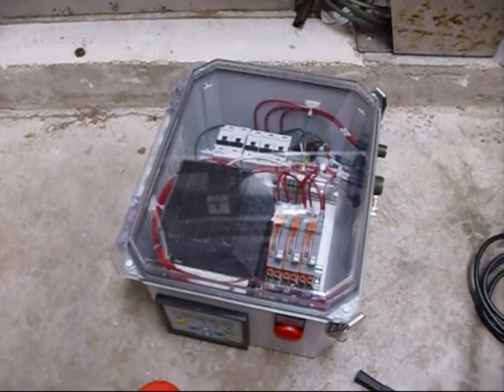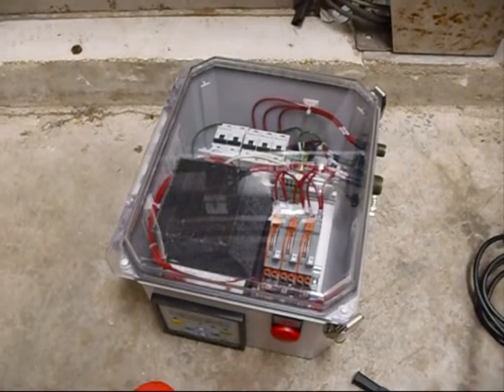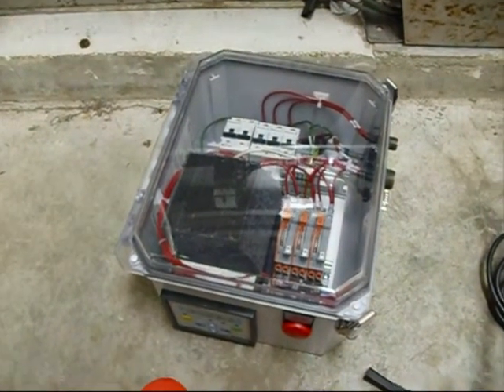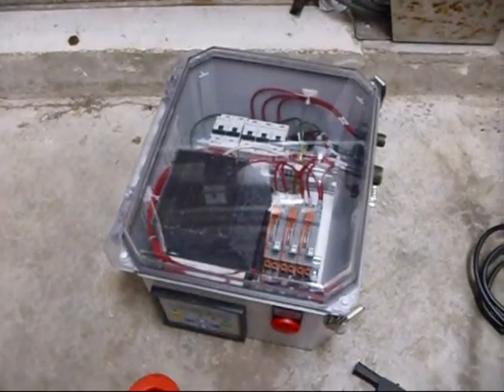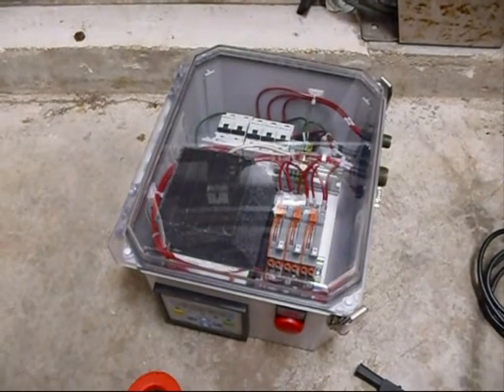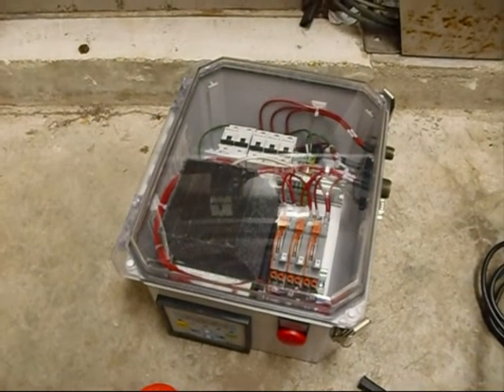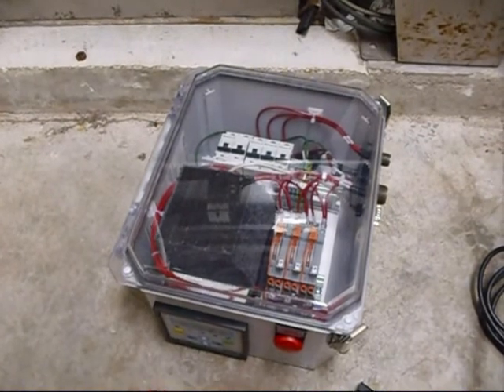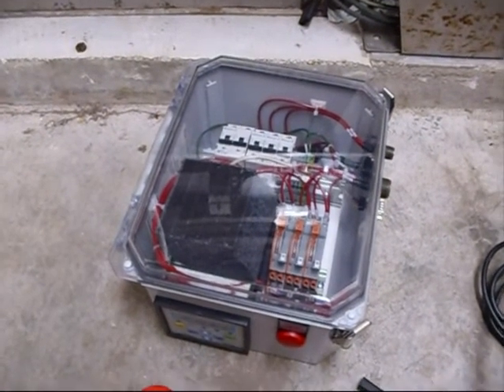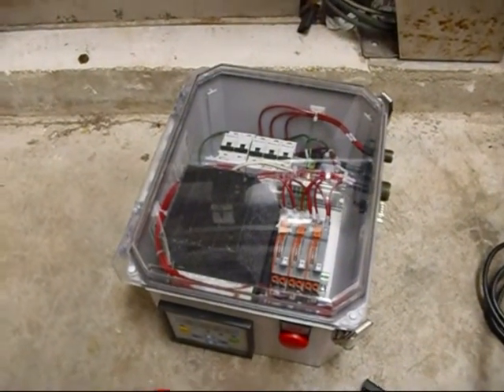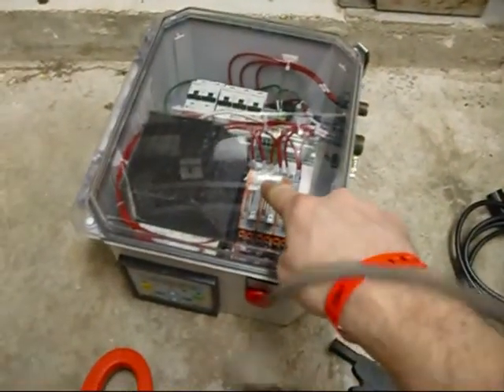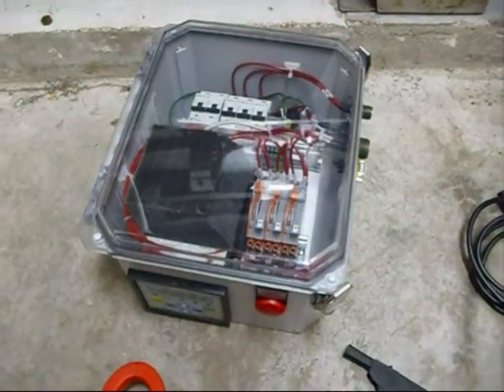Okay, so a brief introduction into the test equipment. The first thing is the MCM box. What we have is a plastic enclosure with an MCM pre-installed. We have 3 breakers for the voltage connections. We have a single pole breaker for the power connection. We have 3 shorting links for the CTs.